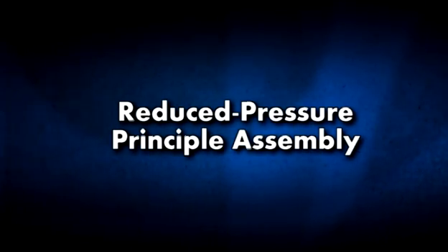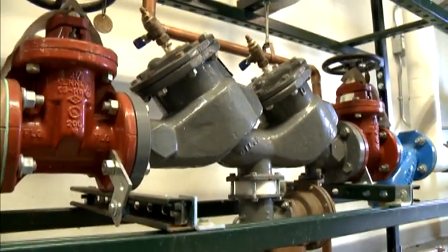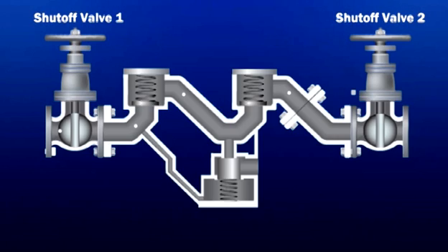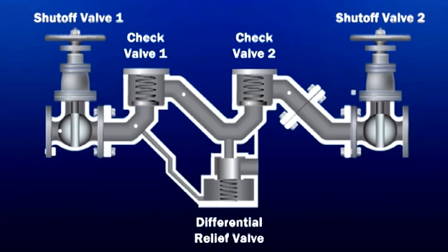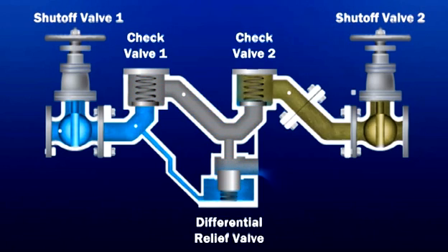Reduced pressure principal backflow preventers, or RP, provide maximum protection against back pressure and back siphonage conditions. This device consists of two spring-loaded check valves with a pressure differential relief valve located between the checks. Water flows into the first check valve. As the first check opens, it fills the reduced pressure zone and the top of the diaphragm at the relief valve at a minimum of 2 PSIG. If there is back pressure, backflow, or back siphonage, both checks will close and the relief valve will open, venting water to the atmosphere.